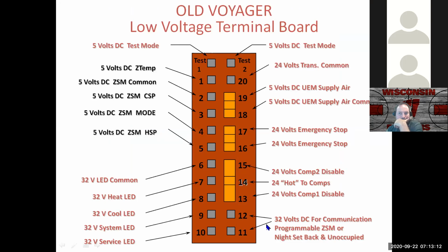But what did change is the terminal strip got smaller, and 13, 14, and 15 is our compressor disable. So this is where you would wire in a frostat or something like that. If you get on these units and these jumpers are gone and somebody has wires on here, that means that somebody's added a frostat, and that could be causing you some of your problems. 16 and 17 are your emergency stop.